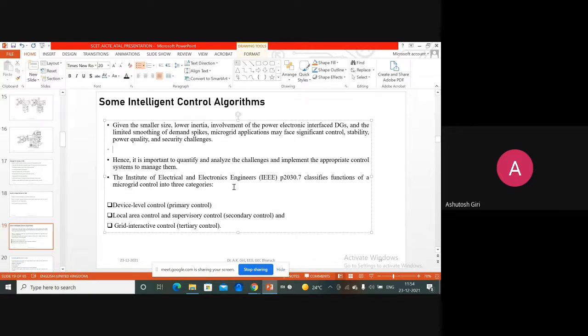The Institute of Electrical and Electronics Engineers, IEEE, as we know, has a standard which classifies the functions of microgrid control into 3 categories. Basically, these are provisional standards. People are still working, IEEE societies are working to define the microgrid codes and standards, but these are the provisional standards, and they say we have to use this kind of control. Device level control is known as primary control, local area control and supervisory control is known as secondary control, and grid interactive control is tertiary control.